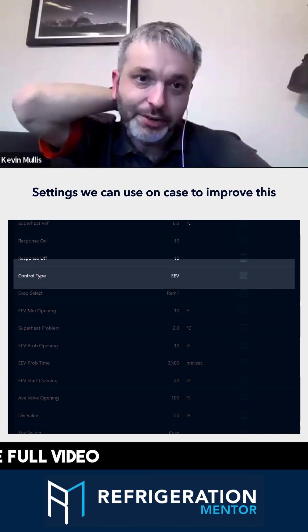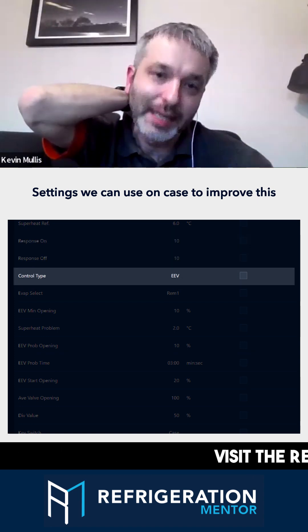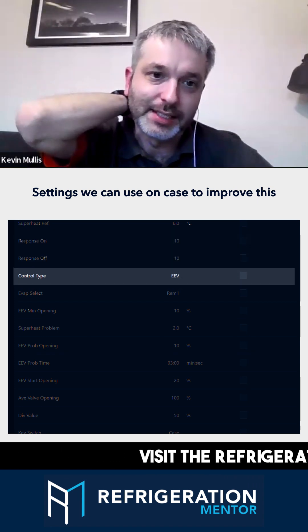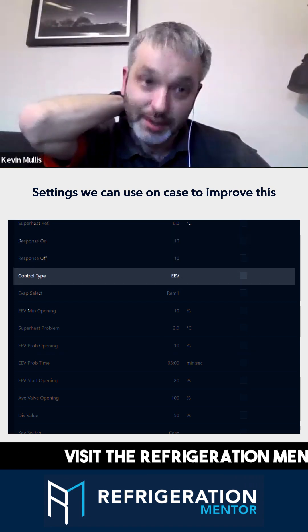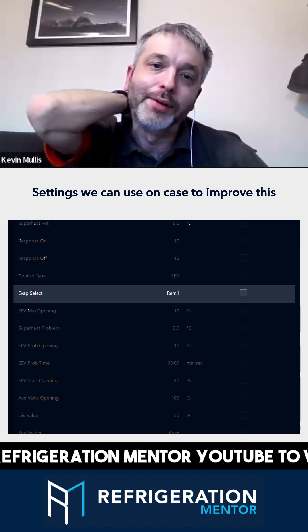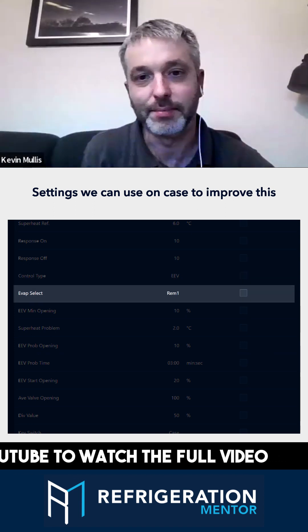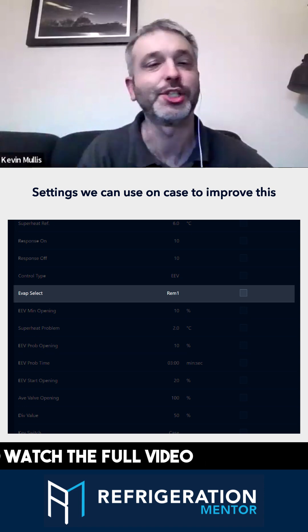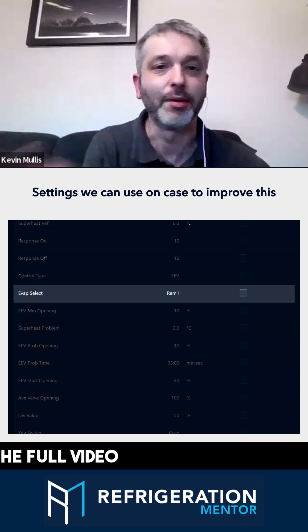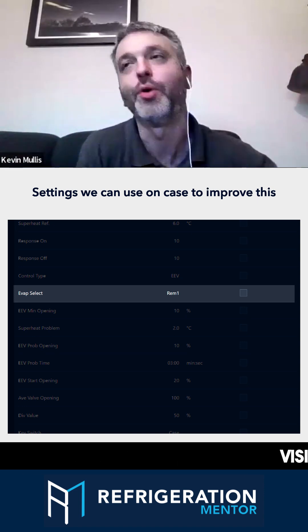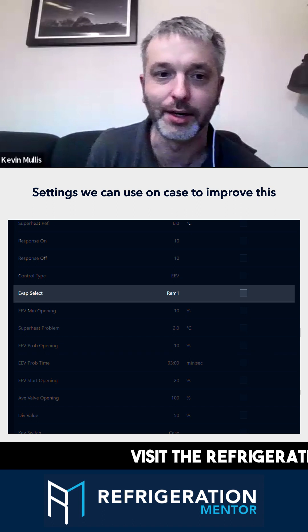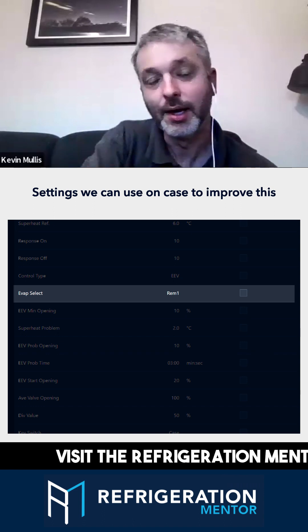As you touched on, control type EEV is superheat related. Evaporator select on this, REM1, means it's sourcing the evaporator pressure from a remote source, be that the network or from the local hub it's connected to rather than local transducer.